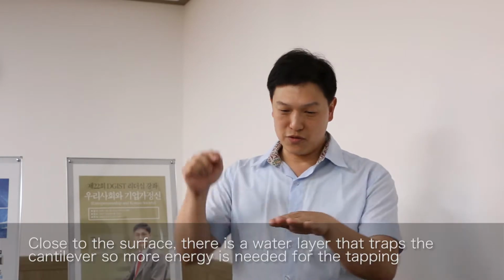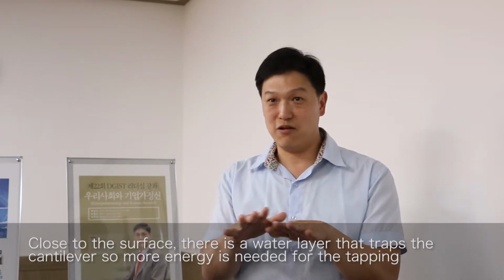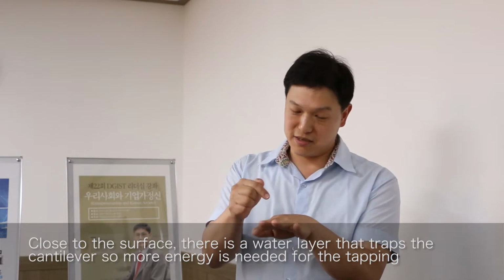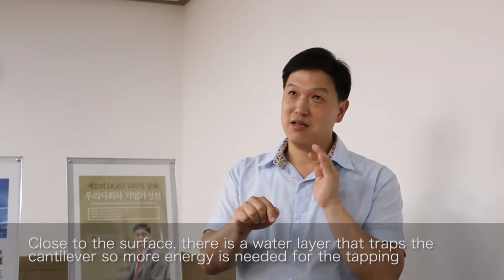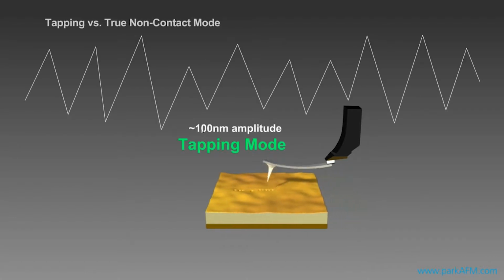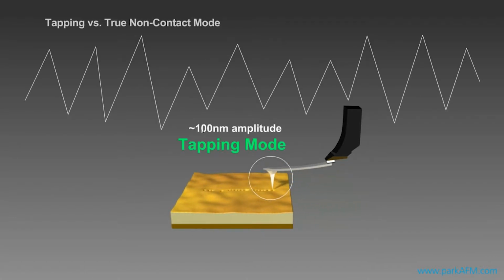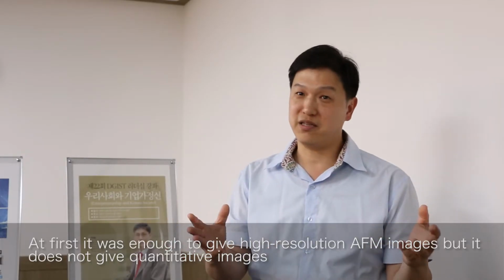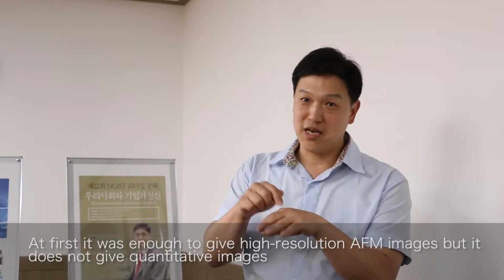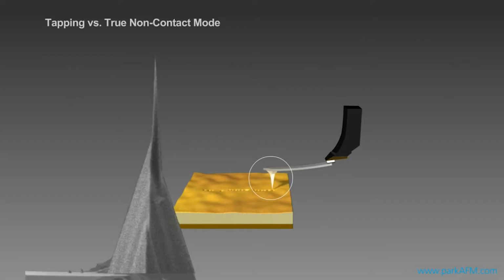So, in tapping mode, when the tip is close to the surface, there's always a water layer trapping these cantilevers. So they use much higher force or higher energy to tap, to escape from the water trapping. This way, they do imaging. But it was enough to give high resolution AFM images, but it doesn't give quantitative images, because when it touches the surface, it changes the probe shape. That means it will change the data over time.